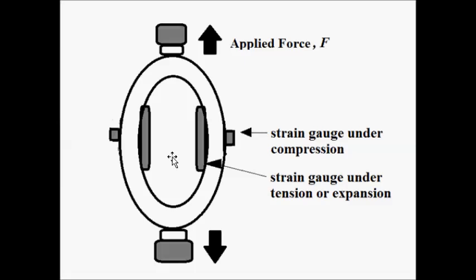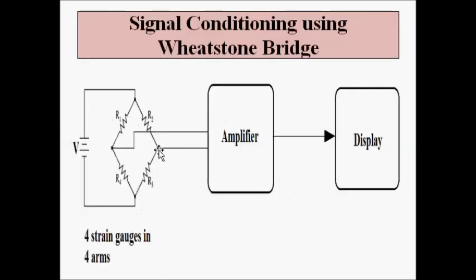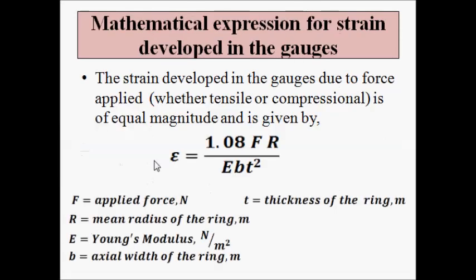The changes in strain cause a change in the resistance of the strain gauges, which is converted into a suitable voltage signal with the help of a Wheatstone bridge. The output voltage is amplified and fed to a display unit. The mathematical expression for both tensile and compressional strain is ε = 1.08·F·R/(E·b·t²), and they are equal in magnitude — which is the interesting feature of the proving ring type load cell.